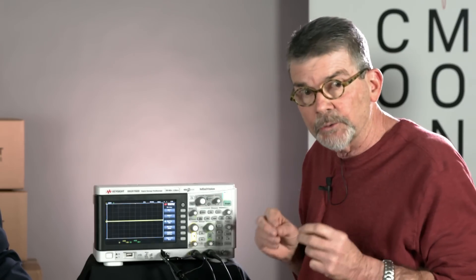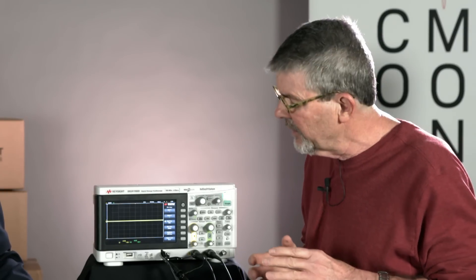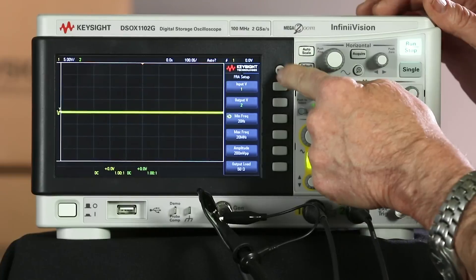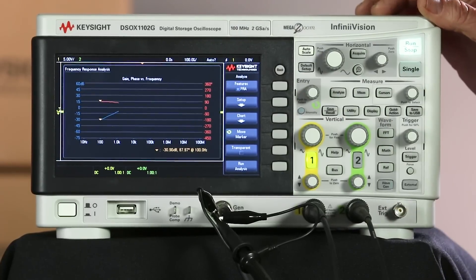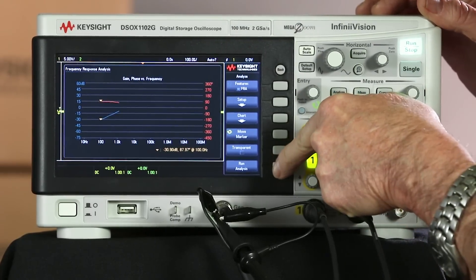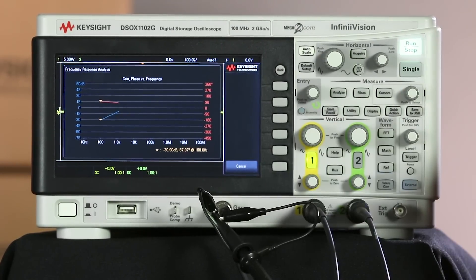Now, the amplitude, this is in volts peak to peak. Now, most standalone frequency response analyzers or network analyzers typically have them set in either voltage RMS or DVM. So you just need to do the conversion if you're going to compare apples to apples. So we'll press the back key. And the next thing is just press run analysis.